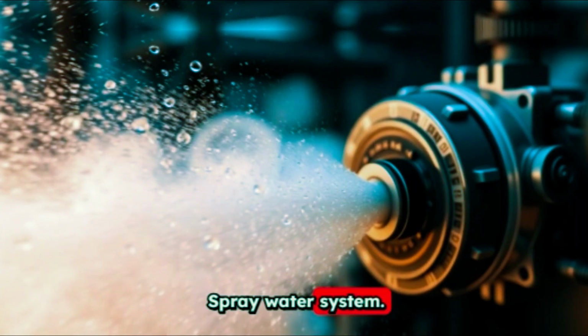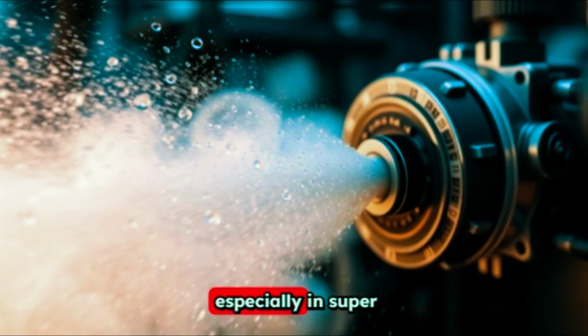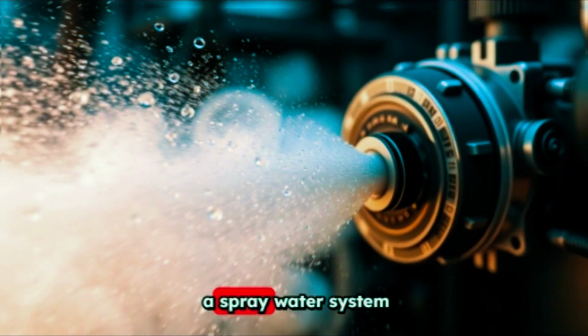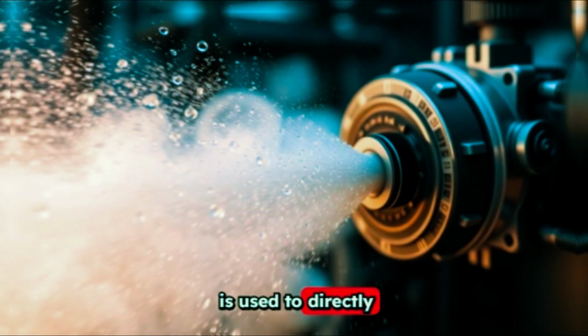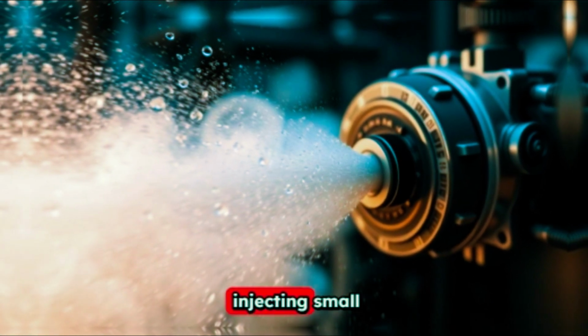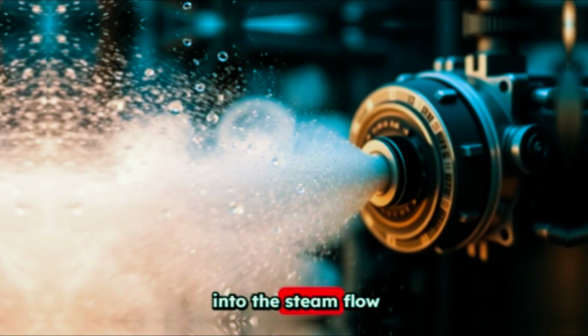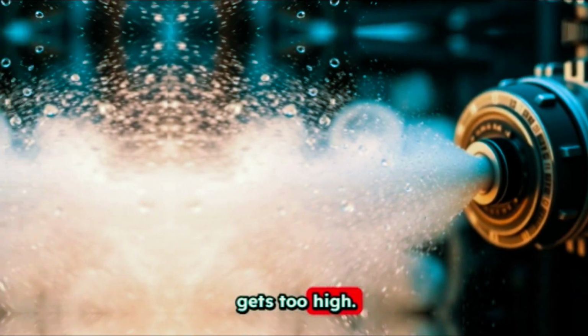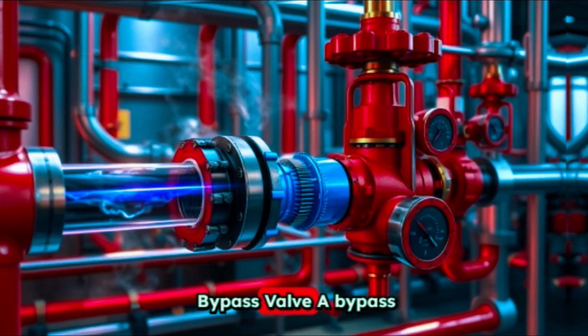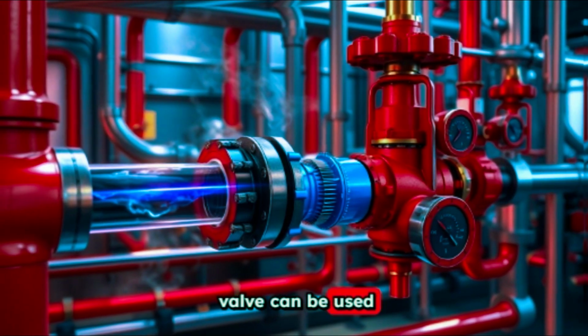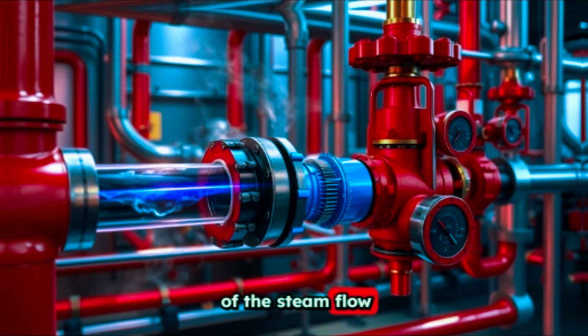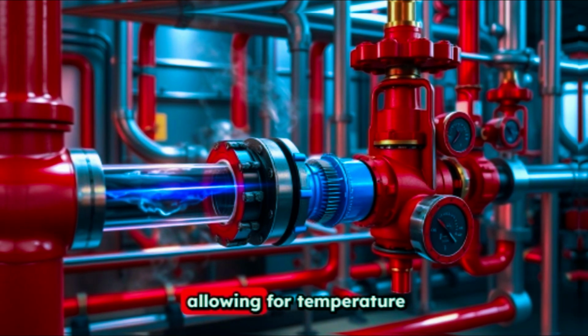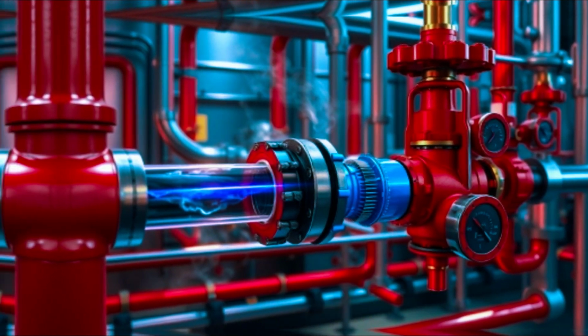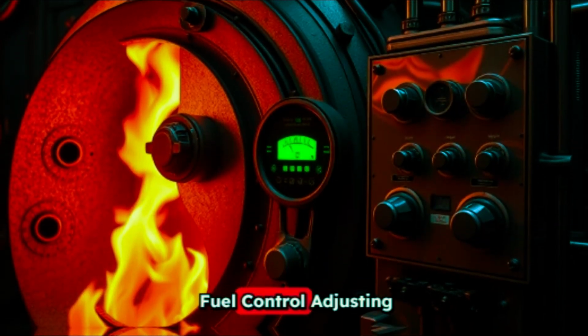Methods for steam temperature control. Spray water system: in many cases, especially in superheaters, a spray water system is used to directly cool the steam by injecting small amounts of water into the steam flow when the temperature gets too high. Bypass valve: a bypass valve can be used to divert a portion of the steam flow to a cooler area, allowing for temperature modulation.